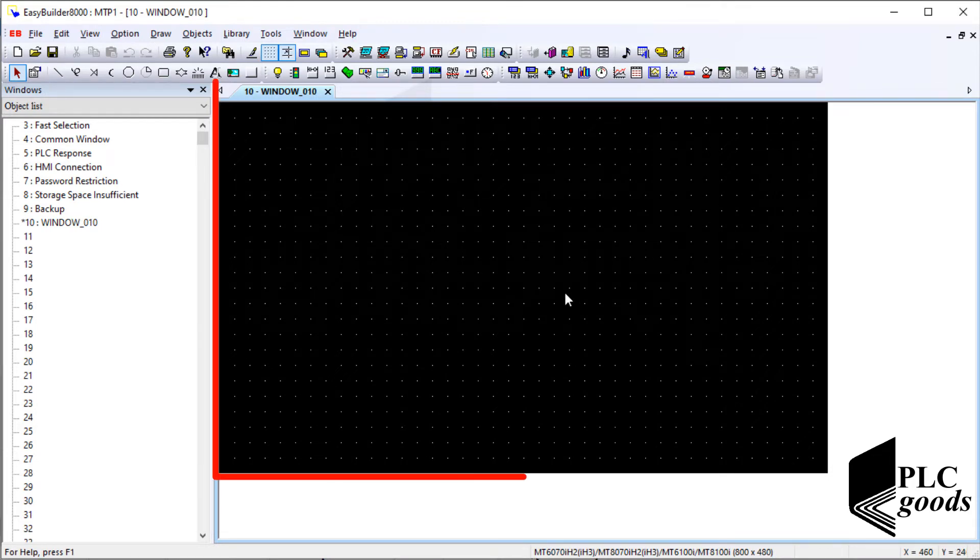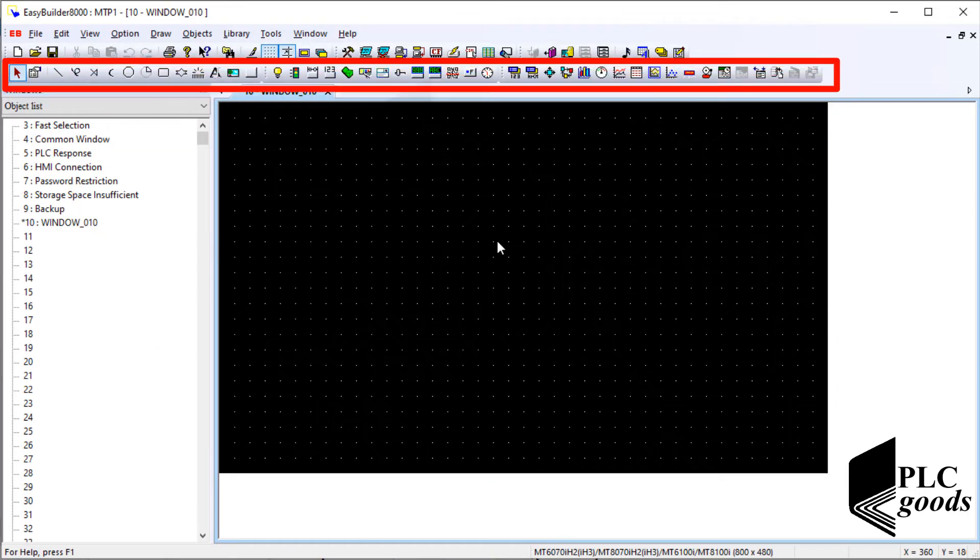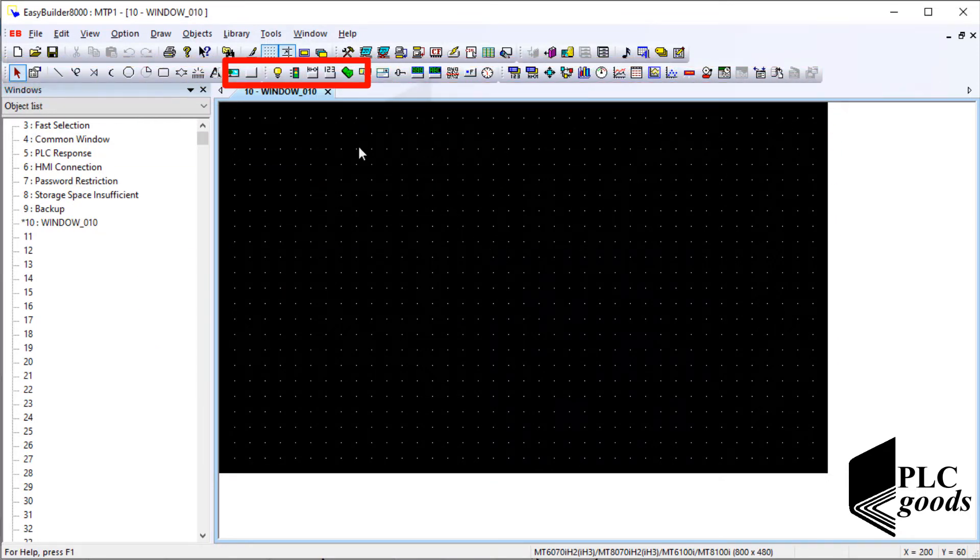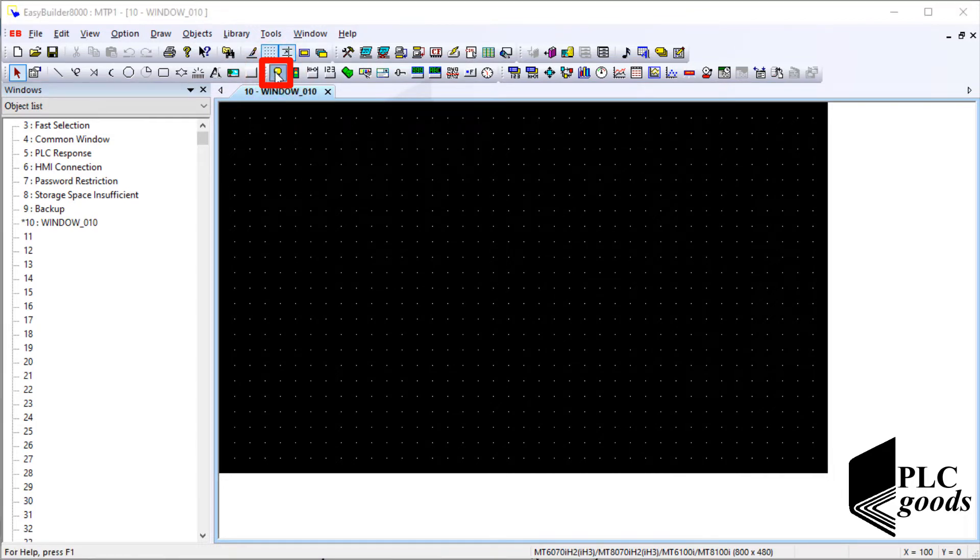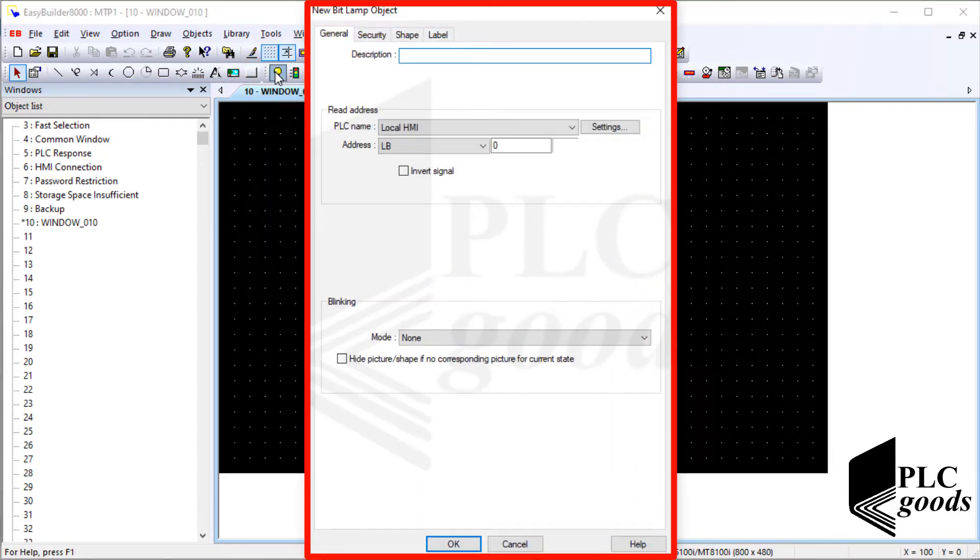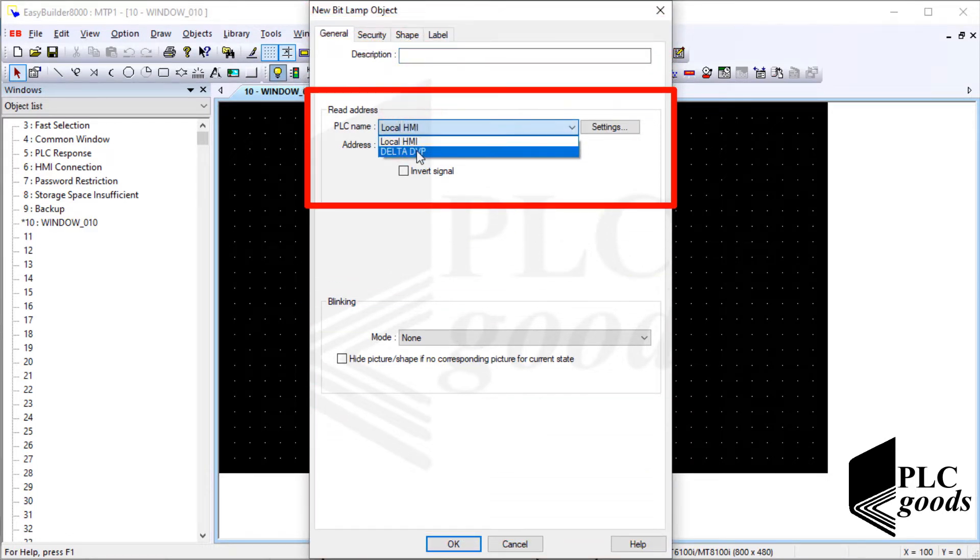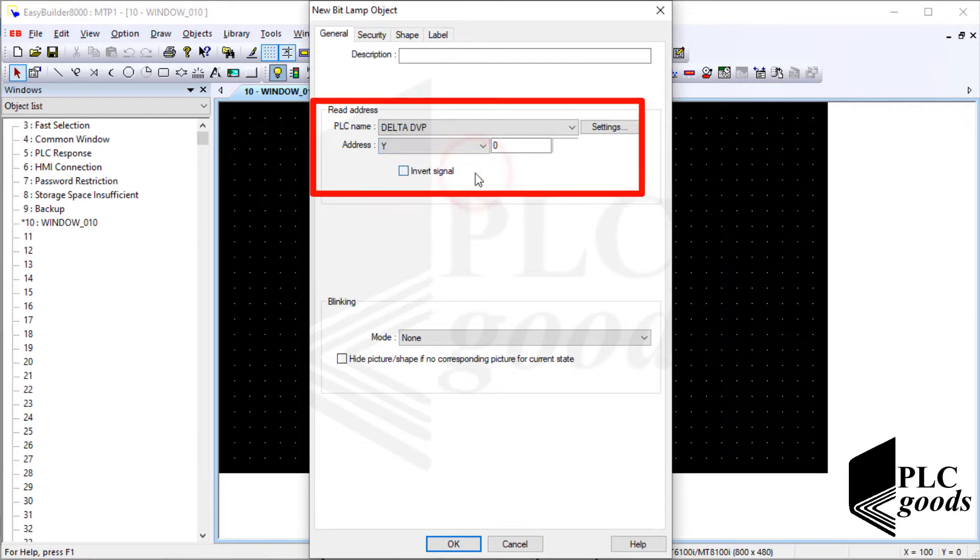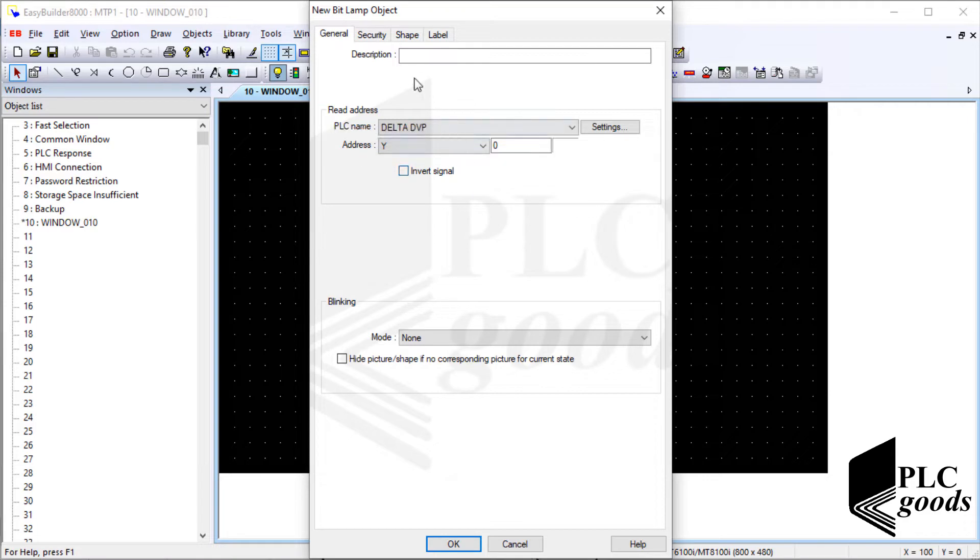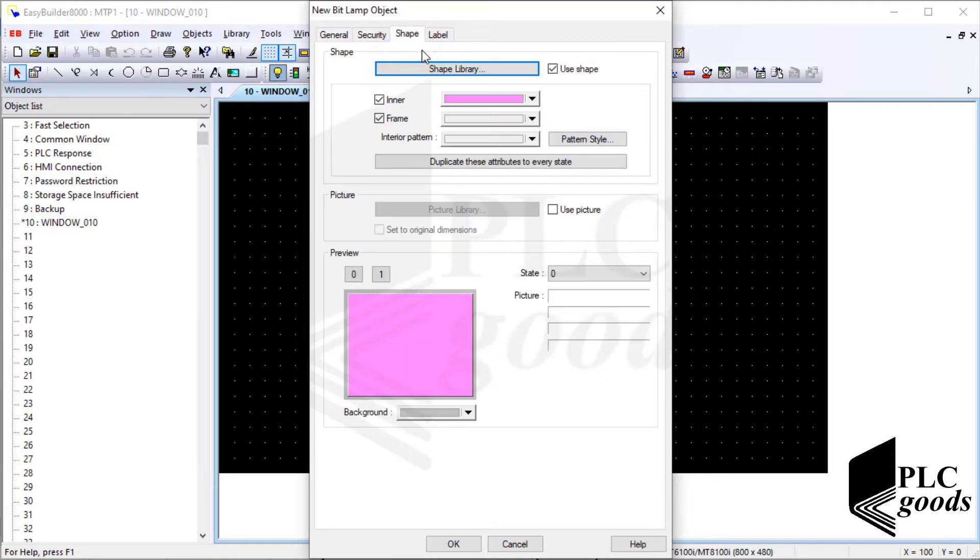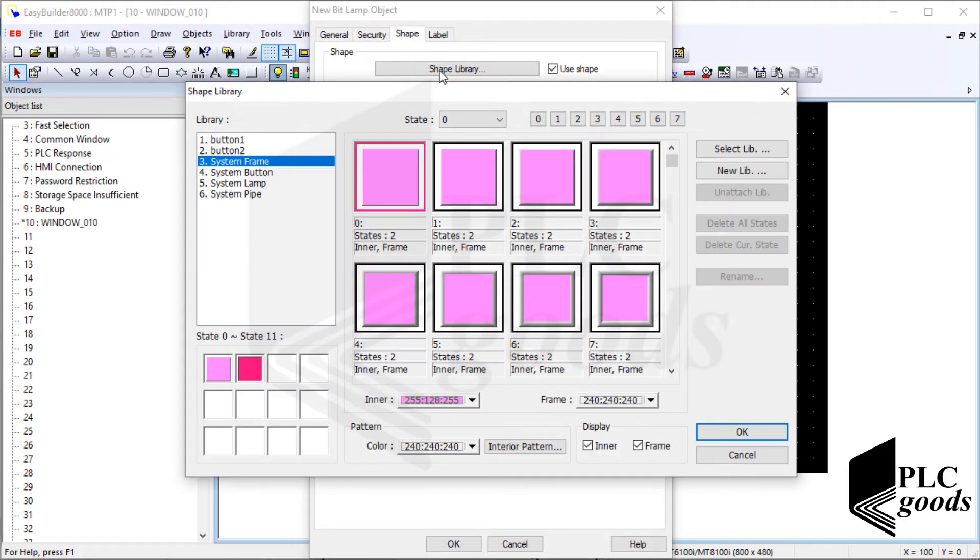Well this area will be displayed on my HMI. I can use these icons to design an HMI screen. Let's start with this one, bit lamp. It can be used to show the state of a bit address of my PLC. So let me select the appropriate connection and then select Y0. Thus the inserted object will display the state of the first digital output. Other settings help us to insert the new object with a suitable shape, color and size.